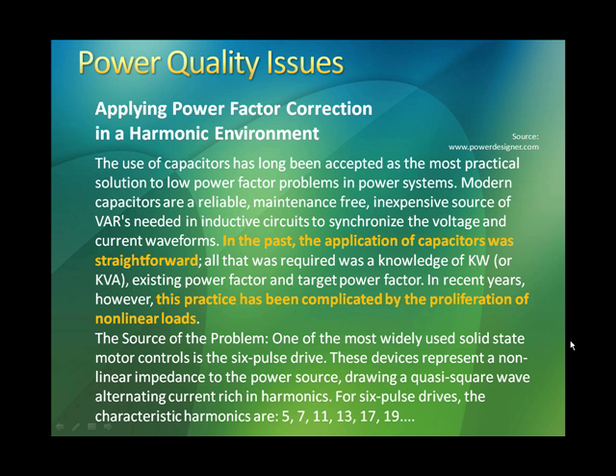Applying power factor correction in a harmonic environment. One of the things we're going to talk about in the next section is reducing reactive energy using power factor correction capacitors. And where you place power factor correction capacitors in a harmonic environment, there is a real potential for problems. Modern capacitors are reliable, maintenance-free, inexpensive sources of the VARs, volt amp reactive energy, needed for inductive circuits. We'll talk about that in a minute. And for nearly a century, capacitors have been used to provide these VARs needed for inductive circuits so that we don't have to supply all of that energy from the utility. It's been straightforward.